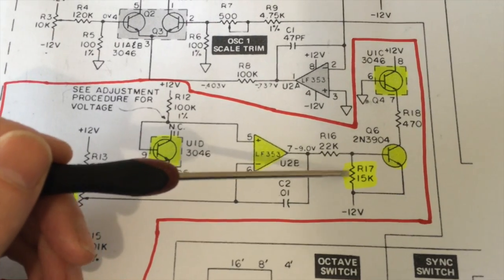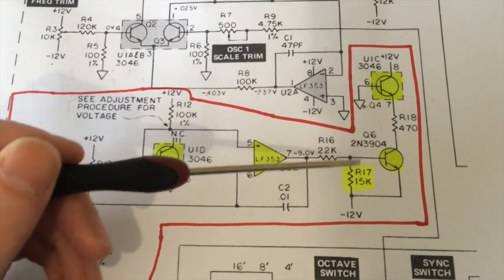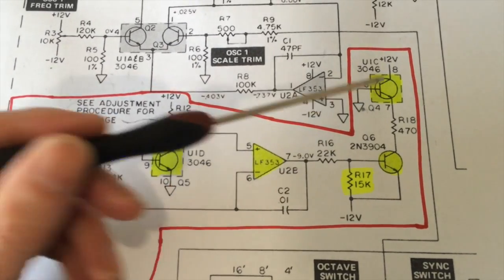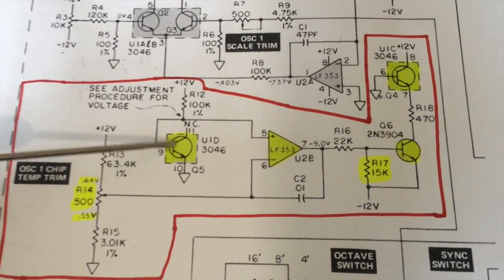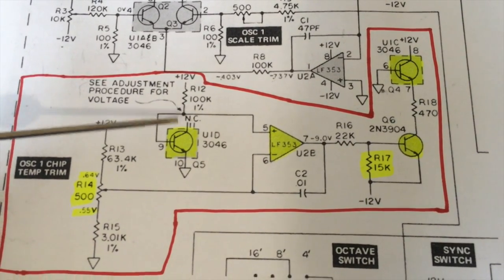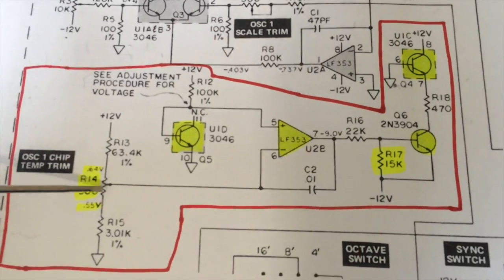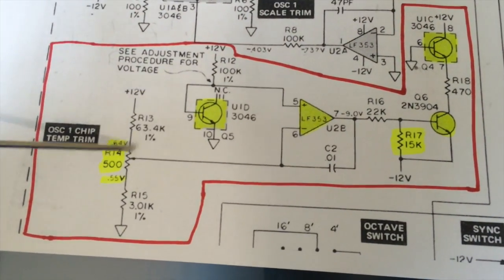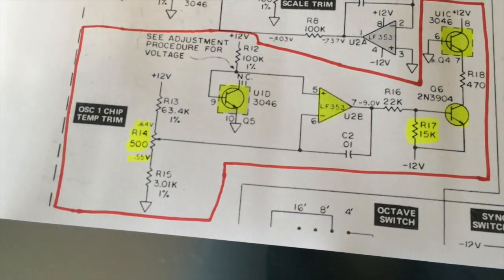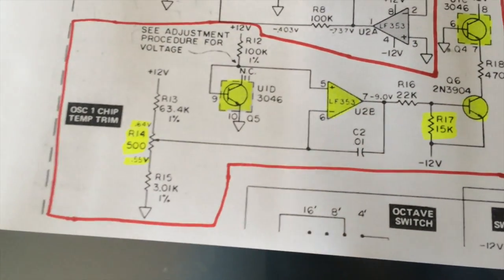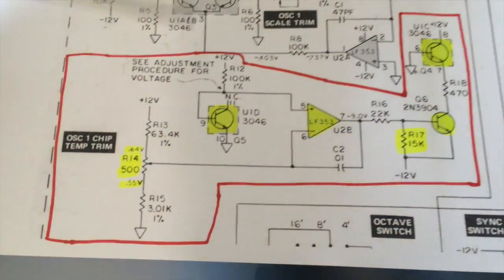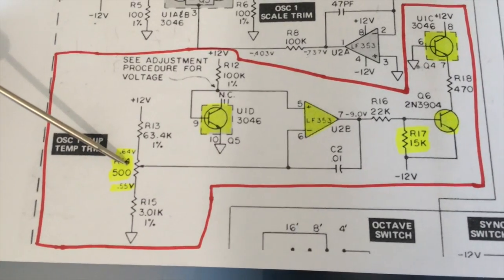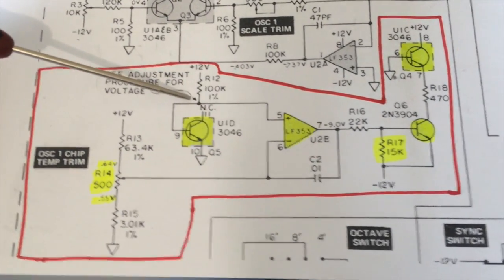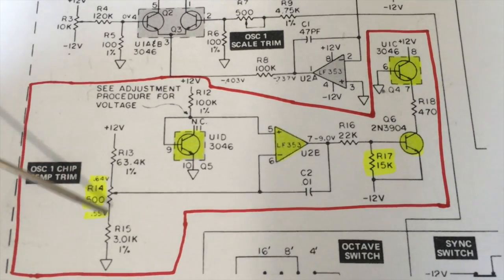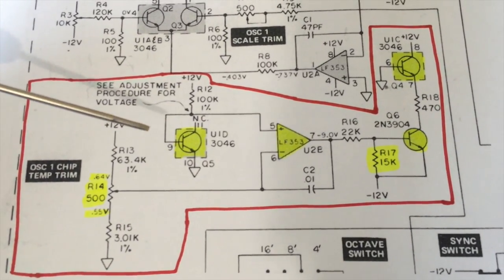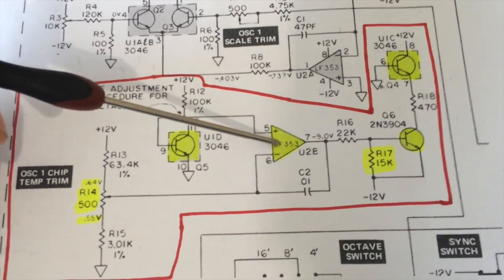And then when we unshort this resistor, this transistor turns on, the heater turns on, we get a temperature change registered at this one, which is where our probe is. And then we adjust this guy according to how the service manual says to get the right temperature, which ends up to be about 55 degrees in the middle of the die on the chip. So when I was adjusting this, I couldn't get any difference in this voltage. I would move this all the way, one way or the other, and I wasn't seeing any change. So either this comparator is not turning on or not turning off or something like that.